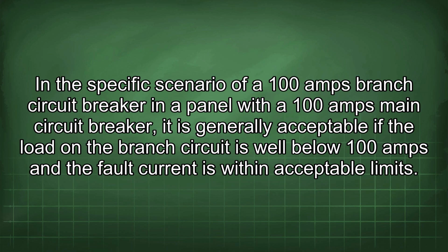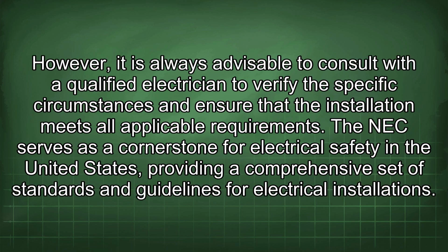In the specific scenario of a 100 amp branch circuit breaker in a panel with a 100 amp main circuit breaker, it is generally acceptable if the load on the branch circuit is well below 100 amps and the fault current is within acceptable limits. However, it is always advisable to consult with a qualified electrician to verify the specific circumstances and ensure that the installation meets all applicable requirements.